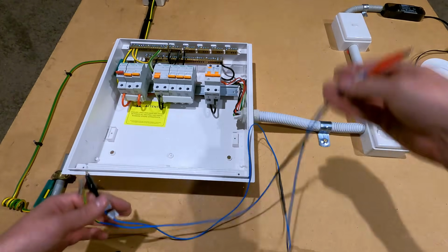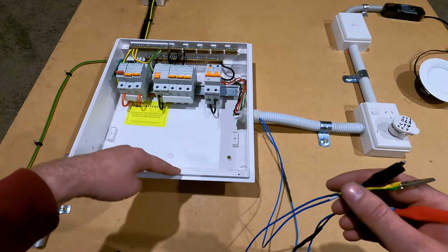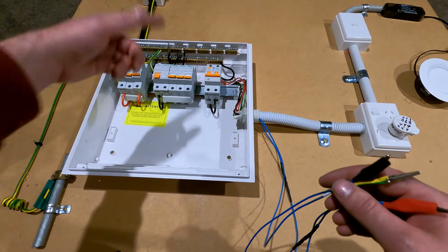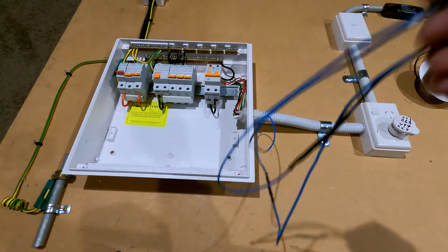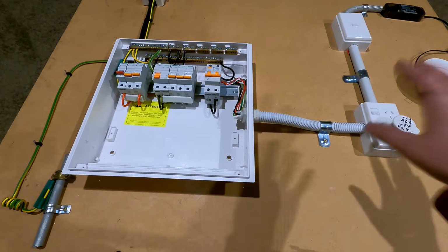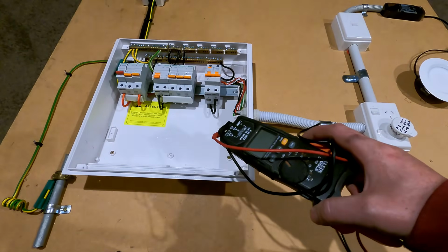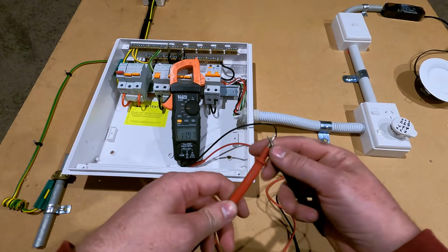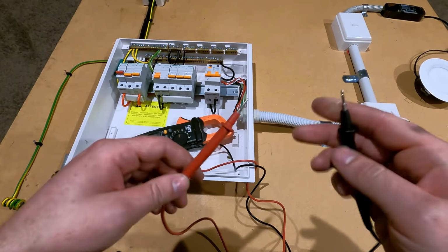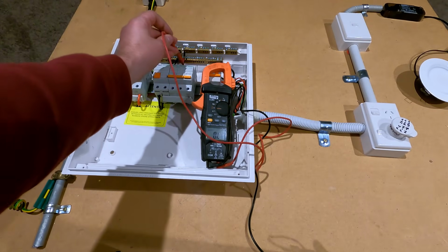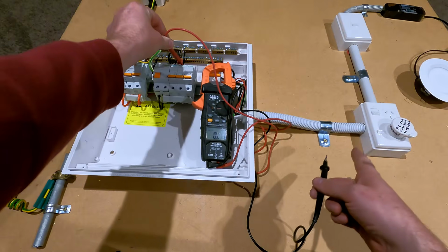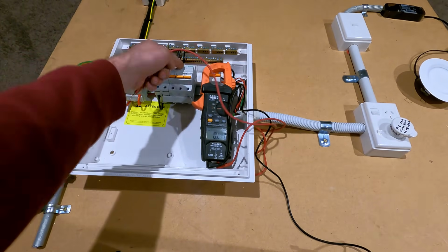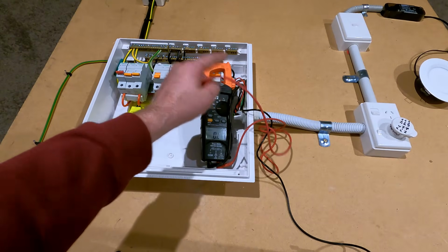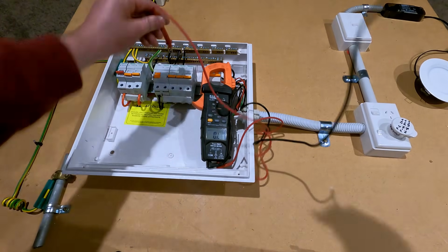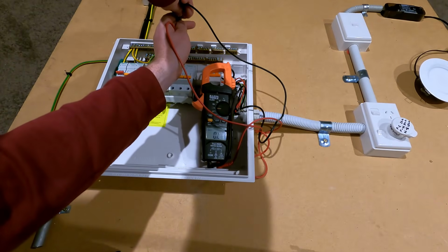So I've made these nice and long. So if I am working on a bigger switchboard than this and the earth bar's down the bottom or the RCD neutrals are at the bottom, then I can go between the bars fairly easily. Alright, so the first polarity test we'll run through will be the socket one. Plug that in properly. Okay, so I've got my meter here. Throw it on resistance and double check. So we've got 0.2 at the moment. And what we'll do with this is we'll throw one on top of the load side of the circuit breaker going out to the socket. I know it's this one, but you just go across the tops of them all until you find the right one if you didn't know. Go from there to the RCD bar.